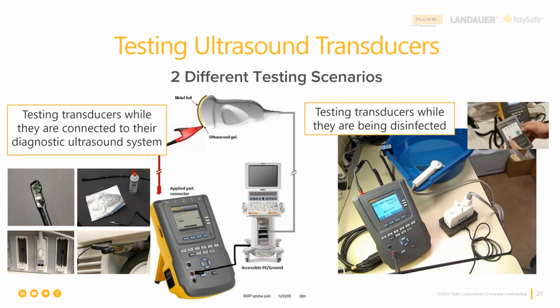So as a result, we need to make specific kinds of patient connection or applied part tests on this TEE transducer. Moreover, the standard of care requires that these TEE transducers be cleaned and disinfected between each and every patient. That's done either in a tub, like you see in the picture on the right, a basin that has disinfectant solution in it. In this case, the disinfectant solution is conductive, but we need to make sure it is sufficiently conductive for the test to be run.